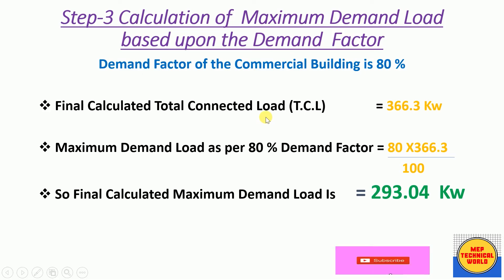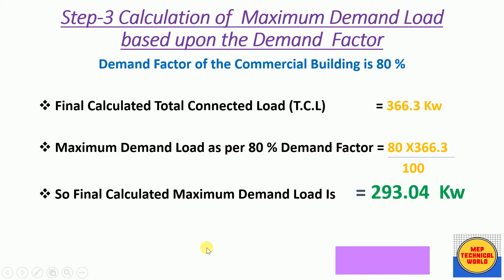The final total connected load including 10% extra is 366.3 kW. Applying the 80% demand factor: maximum demand load = (80 × 366.3) / 100 = 293.04 kW. This maximum demand load is in kilowatts, which is active power.